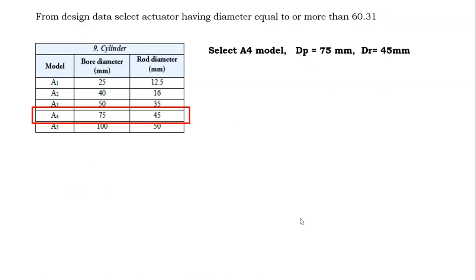From the design data, select the actuator having a diameter equal to or more than 60.31 mm. Select the A4 model, which has a piston diameter of 75 mm and a rod diameter of 45 mm.